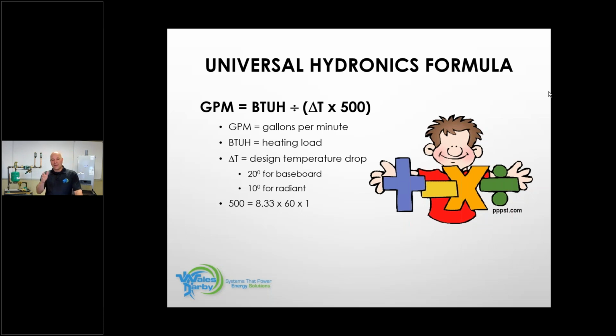So what we do here is that 1 is going to be used as a factor. If you have a 5-gallon bucket of antifreeze or a gallon jug of antifreeze, on that gallon jug or 5-gallon pail, it will give you a factor. I believe we sent out the TACO catalog to everyone. If you go into, I think it's page 44 or 46, it will give you a 30% glycol, a 50% glycol mix within that book. On that pail, you take that factor and you factor it in, and what you're going to find is that 500 no longer becomes 500. It will be a lower number. So the ability of a gallon of liquid in your heating system now has less ability to absorb heat and deliver heat. And that's what this formula is going to help us figure out here.